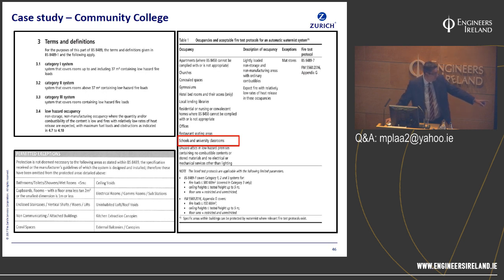Also, if you have a look down here in the permitted exceptions, there's a reason why that water mist system is considerably cheaper than a standard OH1 sprinkler system. For some reason, to make it cheaper than sprinklers, they've omitted all of the protection to the ceiling voids, which would be on a sprinkler system. Electrical rooms have been omitted, which are a key inception hazard in schools and should be protected. No protection to external balconies and canopies. Canopies are a key arson risk within schools, often used as external teaching spaces.